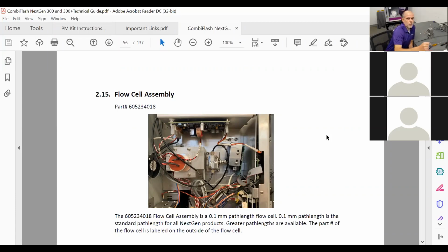So a flow cell for a NextGen is typically going to have a gap of 0.1 millimeters. Remember I was showing you, not with my fingers. The part number for it is 605-234-018. All right. Don't think that you can just improve things in your unit by ordering a wider gap flow cell, and that it may, but we will ask that you keep the standard flow cell in your unit because a lot of other things depend on that as well. Our universal test mix, for example, depends on it being the normal 0.1 millimeter flow gap, okay?